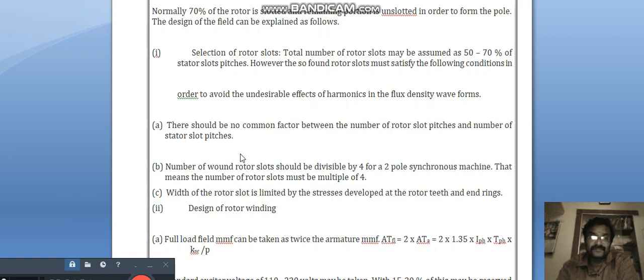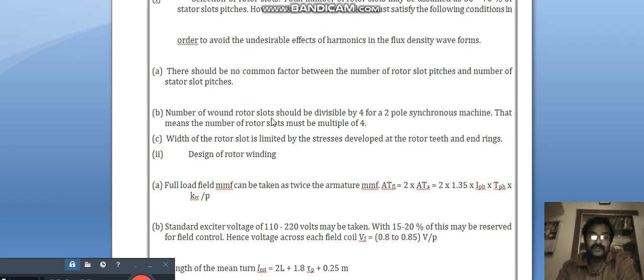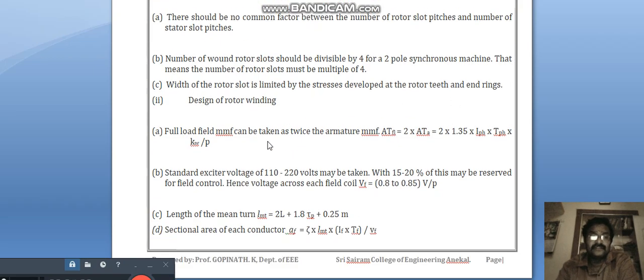There should be no common factor between the number of rotor slot pitches and number of stator slot pitches. Number of wound rotor slots should be divisible by 4 for a two-pole synchronous machine, that means the number of rotor slots must be multiple of 4. Width of the rotor slot is limited by the stress developed at the rotor teeth and the end rings.